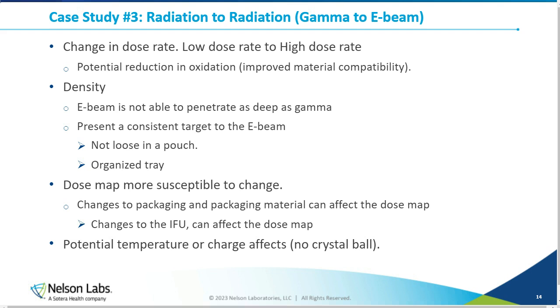The other thing is, whenever we make a change from gamma to E-beam, or really any of the modalities, we really need to demonstrate that the microbial effectiveness is still there. So we probably don't need to do a whole new validation, but we generally are going to be looking at doing something such as a verification dose experiment, which generally we're going to handle by doing a new dose audit to show that the change in modality is still able to effectively kill all of the bioburden that we need to in order to achieve sterility.